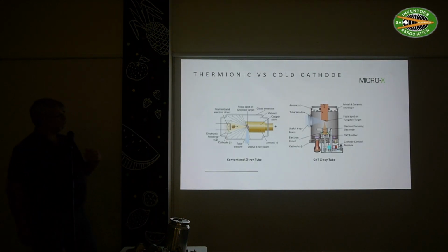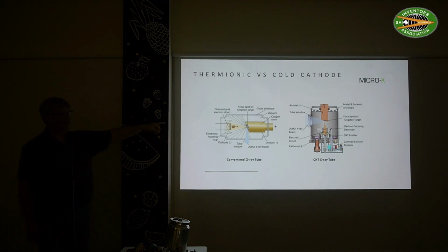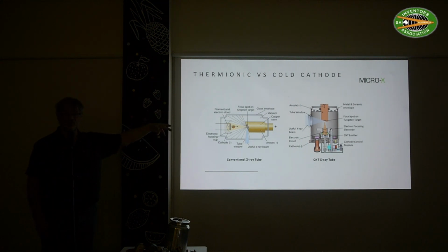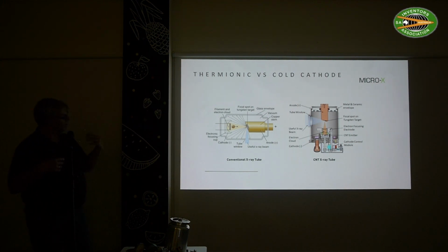So, comparing these things together, the classic one has a heating element and an anode, and typically that sits in some sort of glass container. That whole thing gets hot. It needs to be shielded, to make sure the X-ray only comes out where you want it to and not everywhere else. It gets hot, so you need to cool it down. Typically with X-ray tubes you put this in a large container, fill the whole thing with oil to cool it, and the whole container is a lead shielded box. Compared to our one, that doesn't get hot.